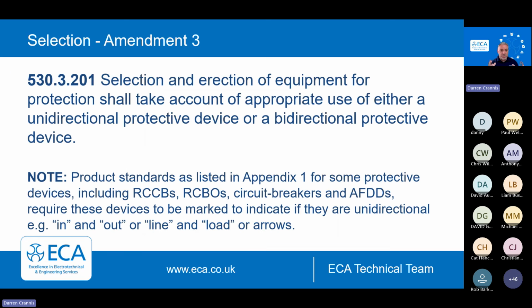That was a fitting time really to come on to Amendment 3. We said we'd talk about Amendment 3 today and the small changes there. It was always a requirement in BS 7671 to wire things up properly and put them in the right terminals the right way, but we didn't really make that clear. So the developers of the standard, the JPEL committees, decided that they would make this crystal clear for users of the standard. A new regulation was brought in, basically saying that we've got to make sure that the equipment is suitable for the direction of energy flow, power flow.